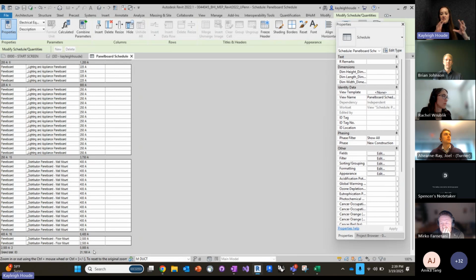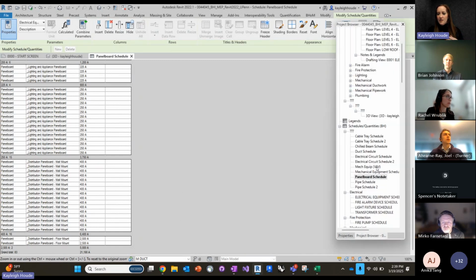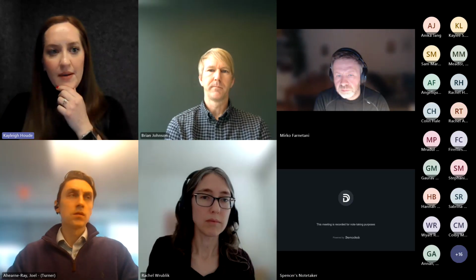Looking at panel sizes as they scaled up felt appropriate for this study, checking whether the size matched what we specified on this project, weight-wise. So scaling by amps: divide the total by 225 to get the quantity associated with the panels. The same thing was done, or maybe I don't have it separated out, for transformers—dividing by 45 or 50 kVA, whatever was specified, to get that scalability by capacity or amps, which was useful in the electrical space.